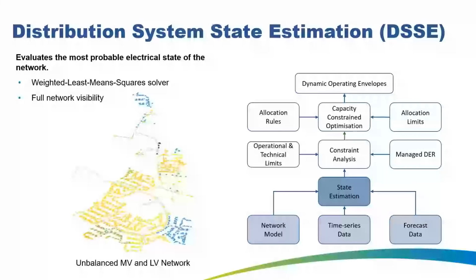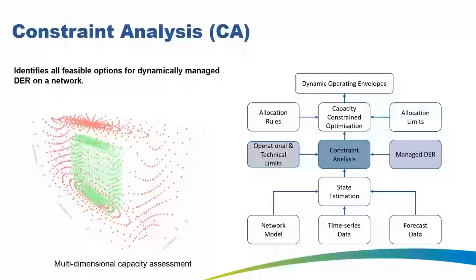The next step after we have that network visibility is to undertake a bit of constraint analysis. What that's doing is identifying feasible options for our dynamically managed DER. Into this we feed in operational and technical limits, so the medium and low voltage limits we want to stay within, limits on capacity, currents flowing through feeders, and we might throw in limits on reverse flow through certain sections of network.